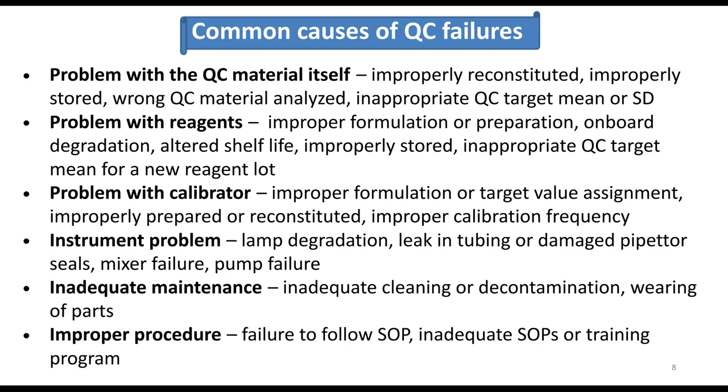So QC can fail with a problem with the calibrator, so improper calibrator formulation or target value assignment by the manufacturer. Calibrators can be improperly prepared or reconstituted by the lab, or the lab could be using the improper calibration frequency. QC can fail due to an instrument problem, so lamp degradation, like for a spectrophotometry assay, a leak in instrument tubing, or damaged pipetter seals, mixer failures, pump failures, all those are common causes of QC failures.